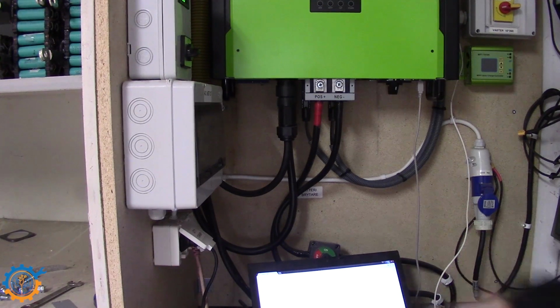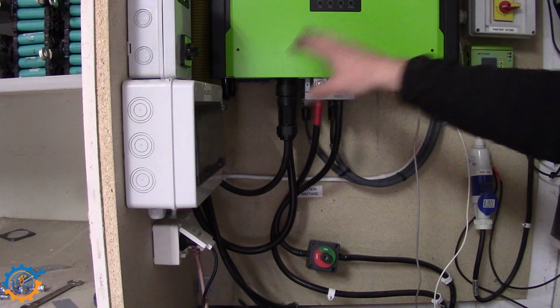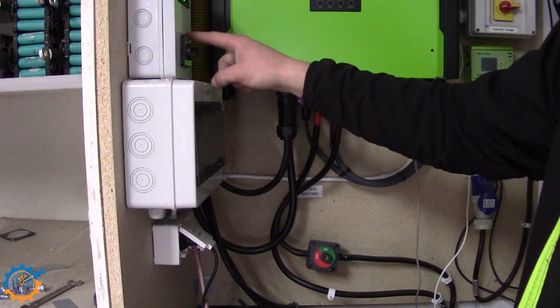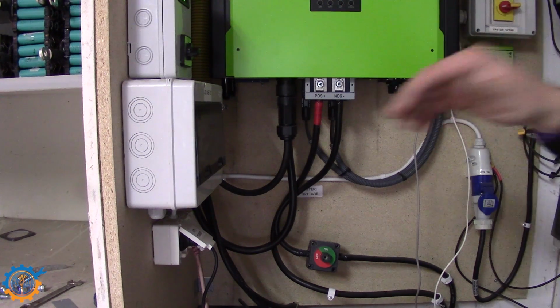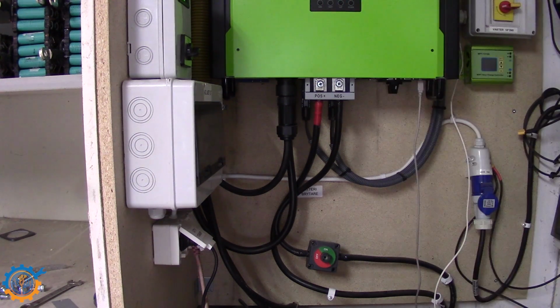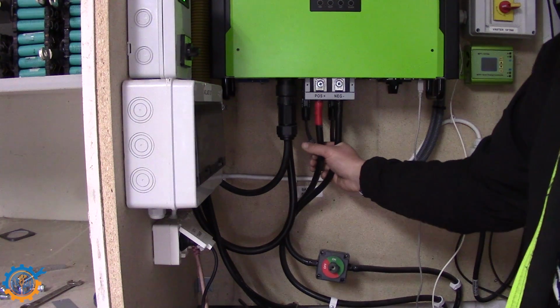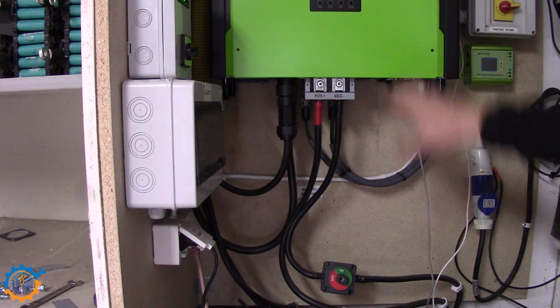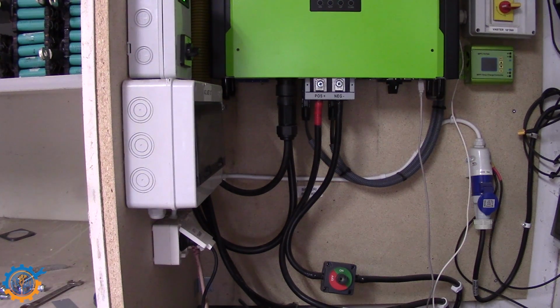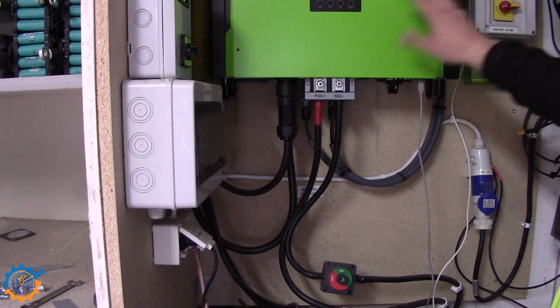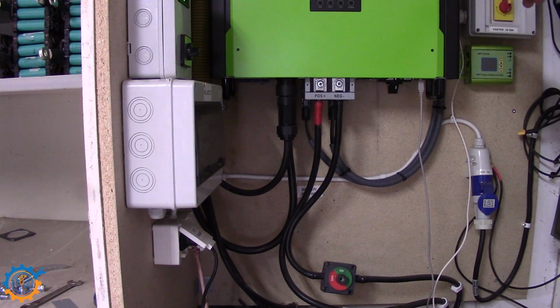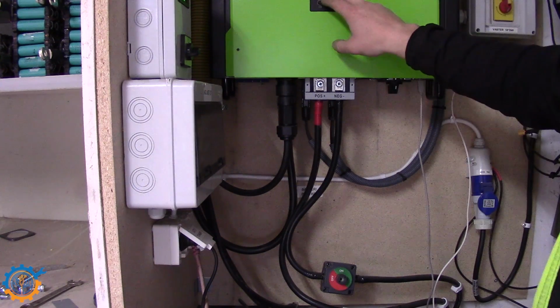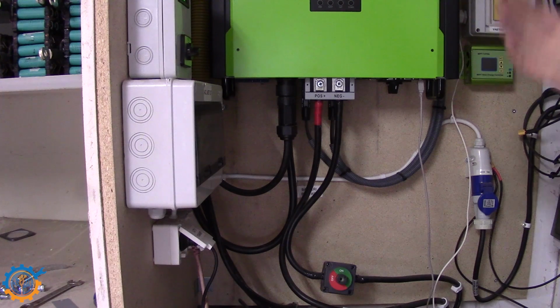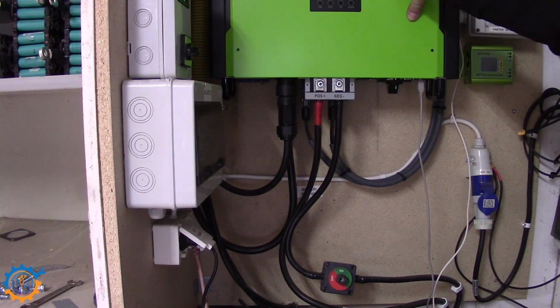Before we start working here, we need to make sure everything is shut down. I connected my AC out to the secondary line, so it's not powered from this anymore. Then it's just a matter of shutting it down - you do it like that, and that goes down. The battery is already disconnected from before, shown here as well, and that's shut down on the computer. Next is to shut down the inverter itself - I disconnect the PV, and when disconnecting the PV only the utility is left, which is why this inverter makes a sound. Then I shut that down too. In a couple of seconds the inverter will shut down - it's just running on the capacitors inside, so it shouldn't take long. There we go.